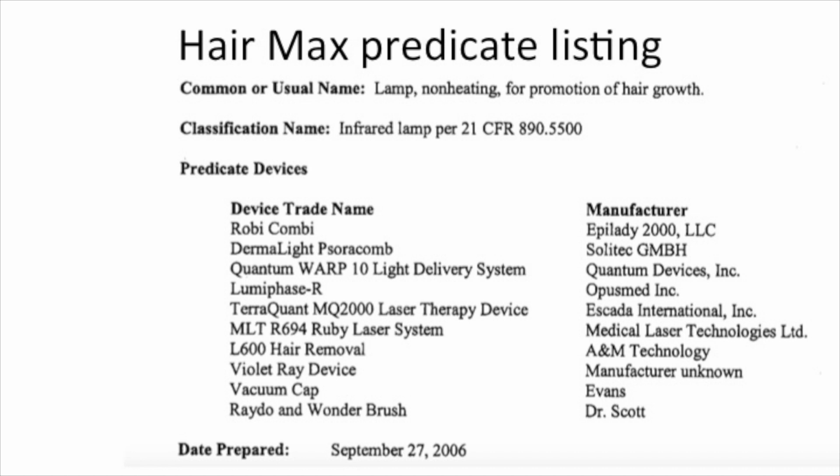Although the substantial equivalence argument paragraph elsewhere inside this summary document covers the bases pretty well with regard to safety and efficacy, the broad swath of 10 devices really wouldn't work today, but it got a clearance back in 2006. Regulatory requirements can change over time, which is why it's helpful to ultimately work with an expert who has recently done something as close to what you are working on as possible.